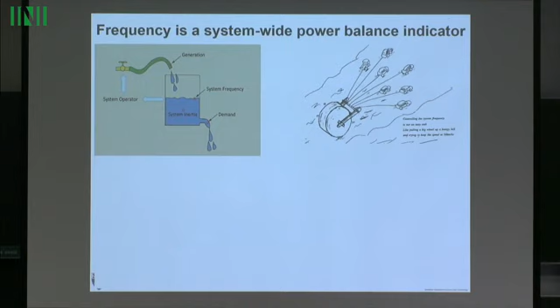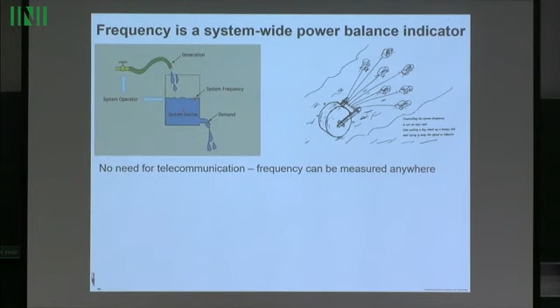Unlike this diagram, where the power system load is a big wheel, and those little cars are generators pulling it up the hill. That hill is not smooth - there will be little bumps, and those generators convey the message of a common frequency, because all those cars go at the same speed. There's also inertia, so if they're going at a certain speed and there are bumps on the road, they'll jump over it. So the beauty of frequency is that there's no need for telecommunication - you can measure frequency at any point in the power system and act accordingly. That's the advantage of the AC system.